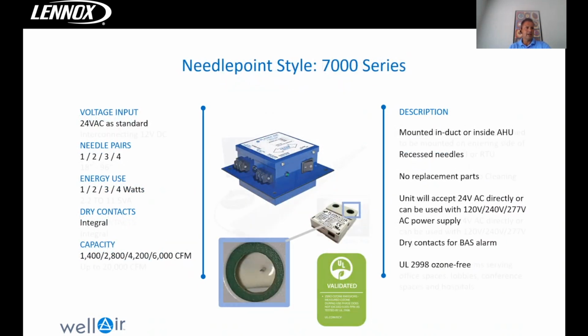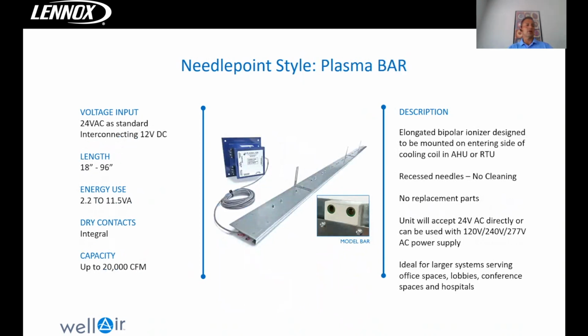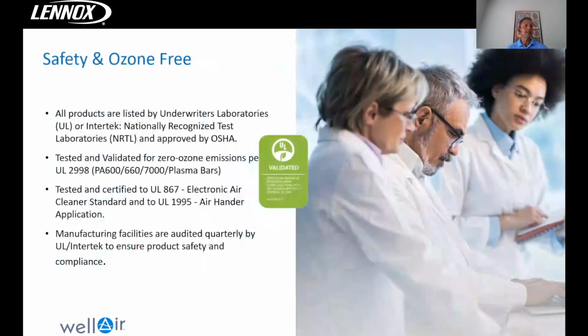And then finally, our plasma bars are meant for larger tonnages, for large equipment, such as up to 20,000 CFM, and the ability to be installed inside of air handlers and rooftop units. Something that is very important, and I invite you to consider when you're looking at ionization and presenting this to your clients, is that we are UL 867 and UL 2998 certified. UL 2998 certification means that you are emitting less than 5 parts per billion of ozone. In other words, you're emitting 0 ozone. And this is a very important designation when you are installing bipolar ionization.